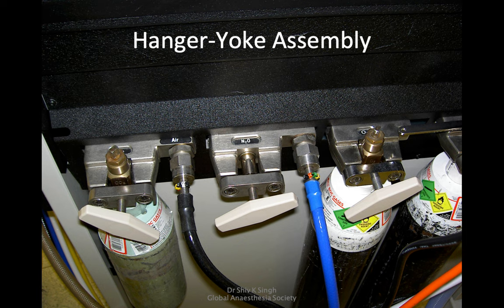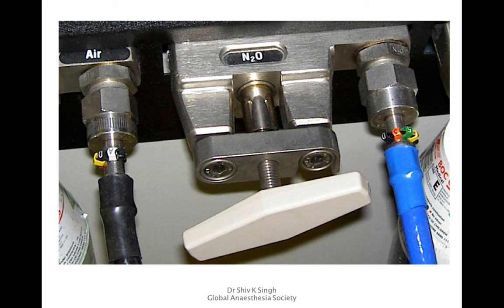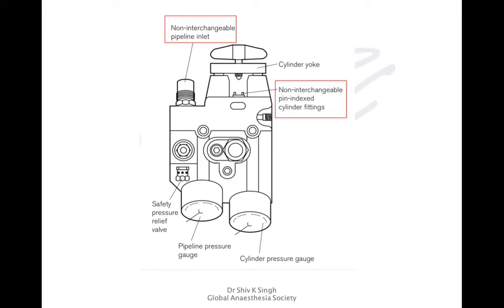The nitrous oxide cylinder has been blanked off using the blanking plug. Oxygen cylinders are also visible. On older machines you may also see a carbon dioxide cylinder, which is no longer seen on modern machines. Cylinders are attached to the machine using the cylinder yoke block assembly with the Pin Index Safety System (PISS). From the pipeline, Non-Interchangeable Screw Threads (NIST) are used at the pipeline inlet.